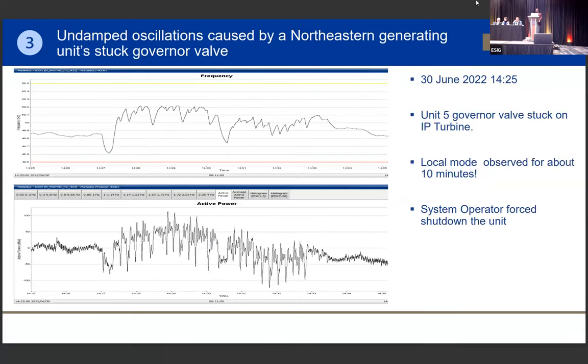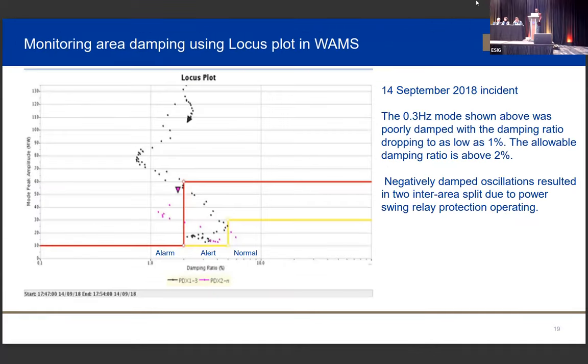Okay, this one was the last one. There was a unit that had a stuck governor. It oscillated for about 10 minutes. So the system operator had to cut it. So currently what we're doing is we monitor the damping on the system using a PMU or WAMS, wide area monitoring system. Whenever we see damping less than 2%, we are most likely to trip the power line or to oscillate. So we're using it a lot.